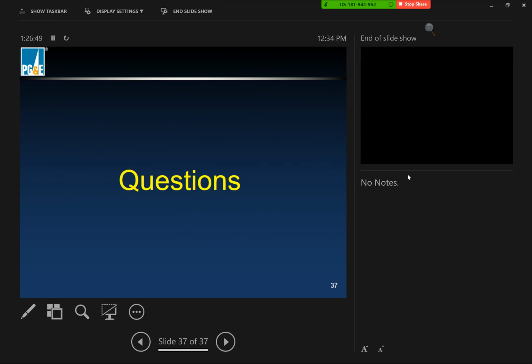Is having a double-ended system more accurate than having a single-ended? I wouldn't say it's more accurate. It should theoretically be the same accuracy. It's definitely more consistent. As long as your clocks are accurate, you will get a double-ended fault location, except if you have taps, then you can only identify, hey, it's somewhere on the tap. But you'll always get a fault location, assuming your clocks are good.